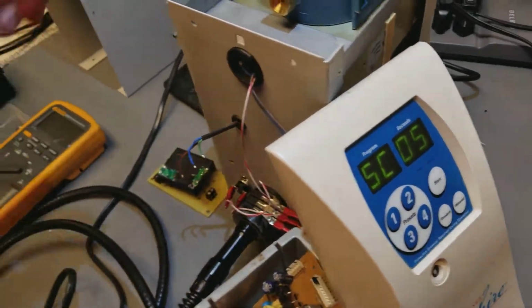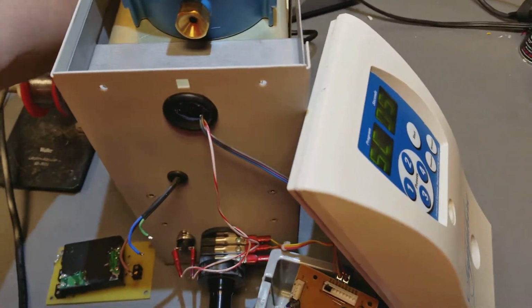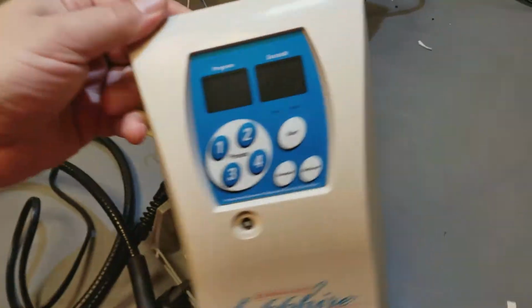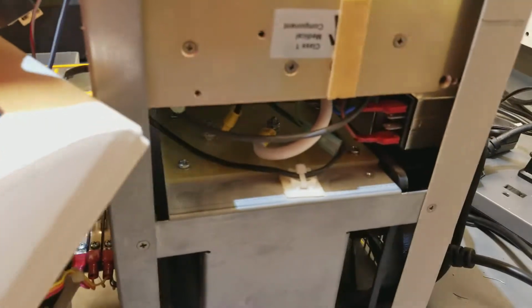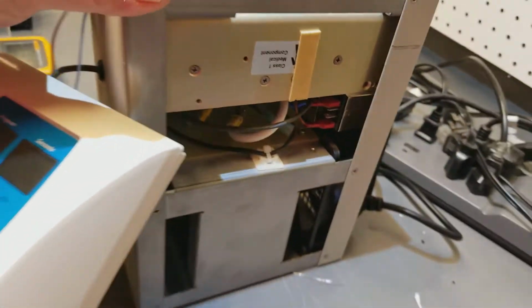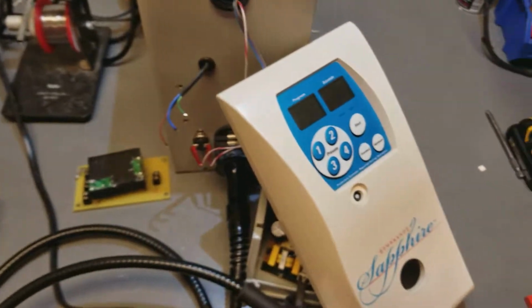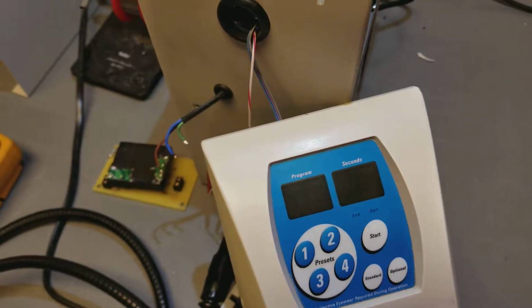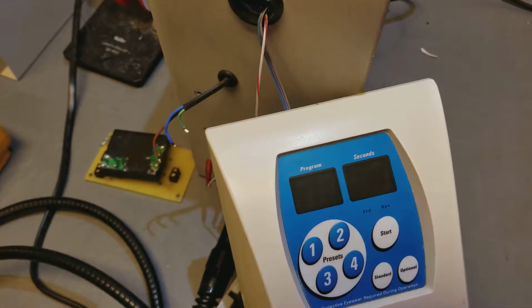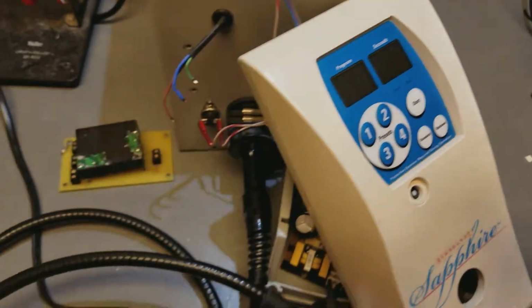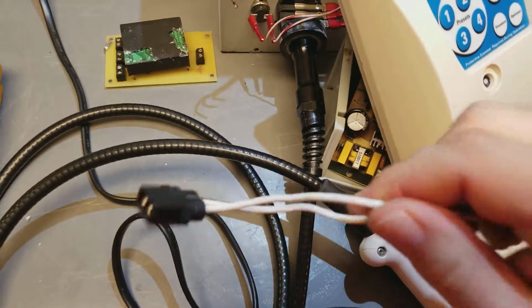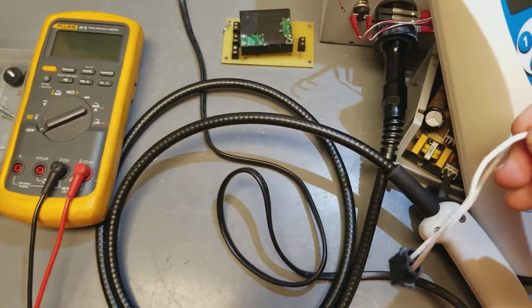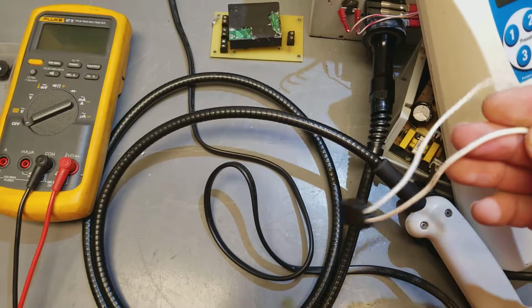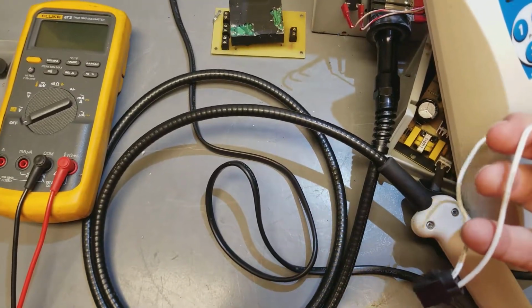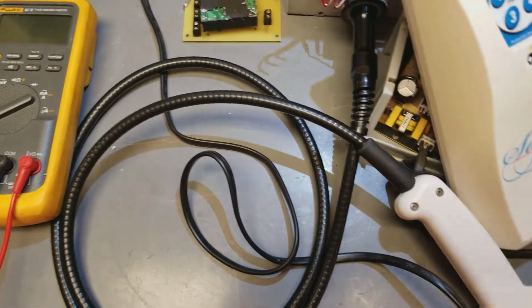Now the other thing I'm going to do, besides fix that power supply, is replace one of the high voltage wires, that yellow connector with the black wire coming out. That's only 600 volt rated cable. I want to put something a bit more conducive for high voltage. I have some bulk wire like this stuff. This stuff is rated at 20,000 volts. No, not this stuff. This is the 600 volt stuff.